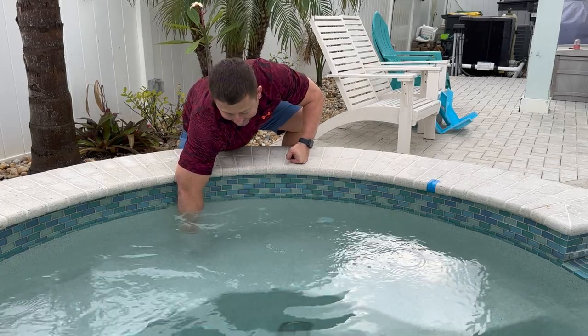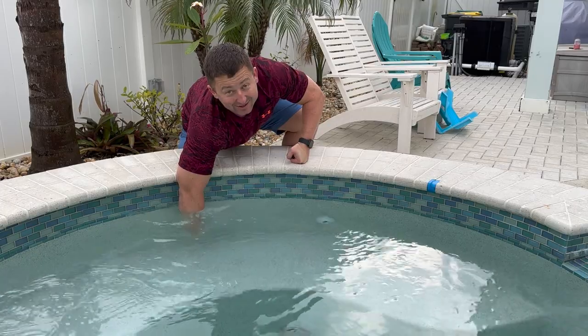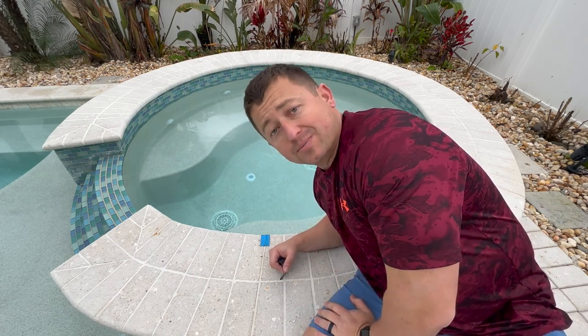It's getting warmer! I know this isn't the correct way to check it, but it's starting to work. So if you have a pool with the IntelliCenter system and an AquaCal heat pump, for whatever reason the new update, firmware version 2.006, is messing with the AquaCal where it doesn't communicate. Switch back to your old firmware like what I just showed you, and you'll be back in business.